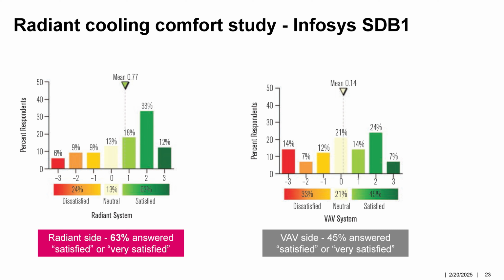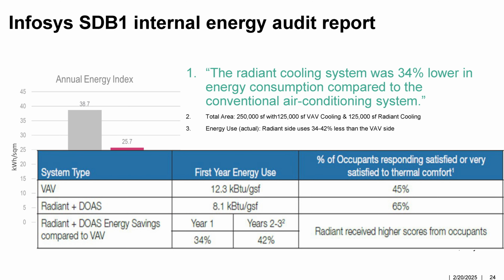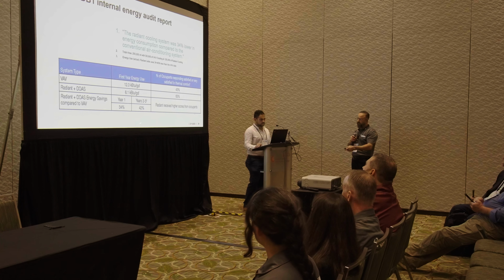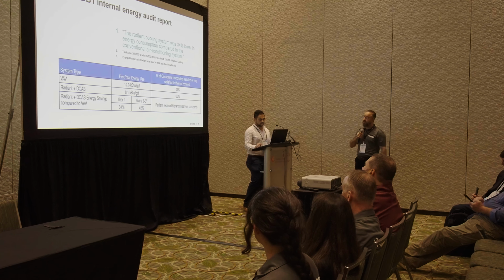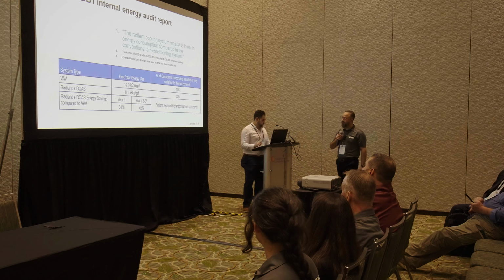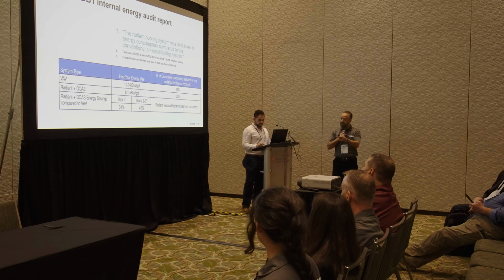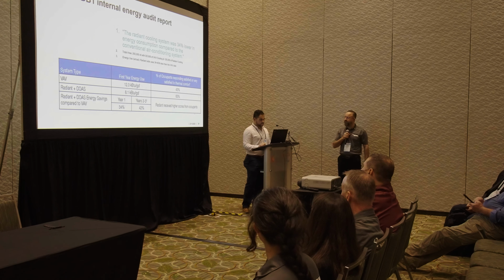Almost 22% more satisfied on the hybrid side, and also around 30% less energy consumption on the hybrid side. That's the overall conclusion here. You can see that in the first year, they saved around 34% on their energy, and then in the second year, by fine-tuning their system, they achieved 40% less energy. And there is your 20% difference in the thermal comfort of the occupants. So please check out the project and share your thoughts.